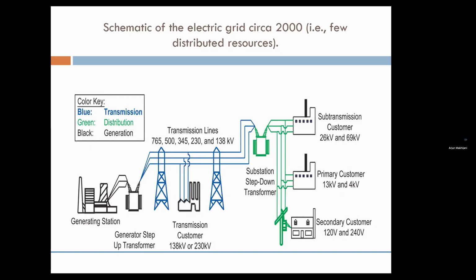The energy isn't generated at very high voltage — maybe 13 or 15 kV, I don't remember the exact number — but you convert it to high voltage, like 765 kV (kilovolts), because the higher the pressure, the lower the current, and losses go as the square of the current. So for long distance transmission you want to increase the voltage — that's what the step-up transformer does. It steps up the voltage from the generating voltage to the numbers shown on top of those blue lines, from 138 up to 765 kV. That's the high voltage transmission system we're talking about today.